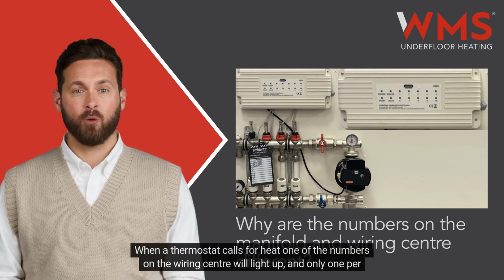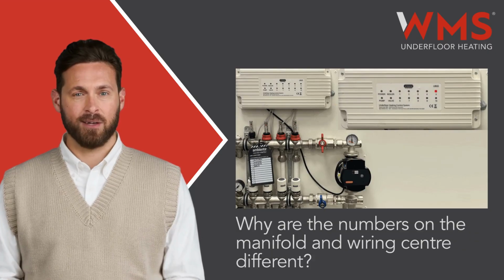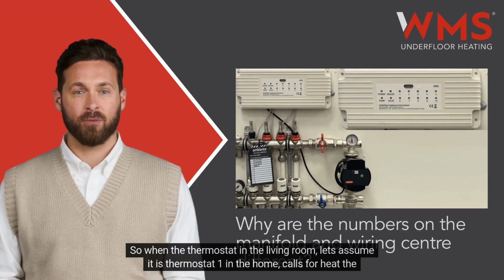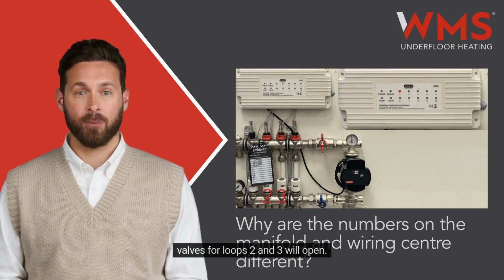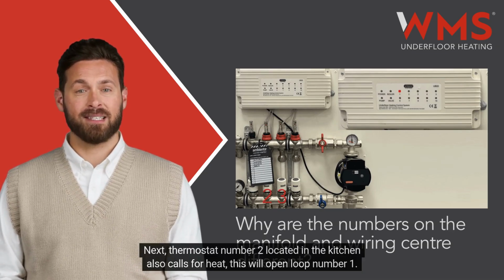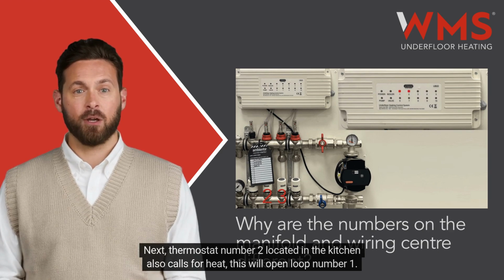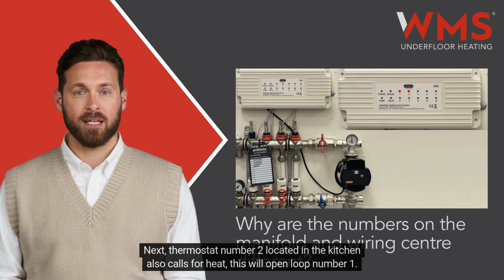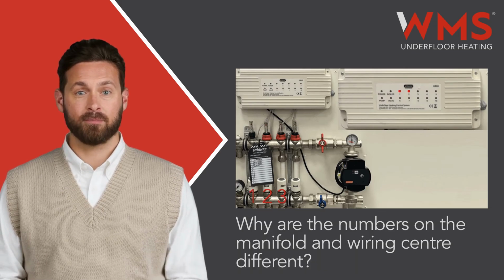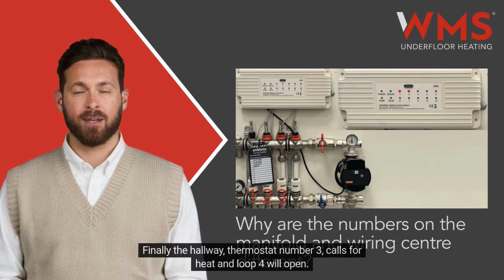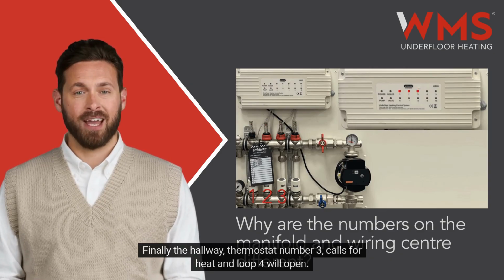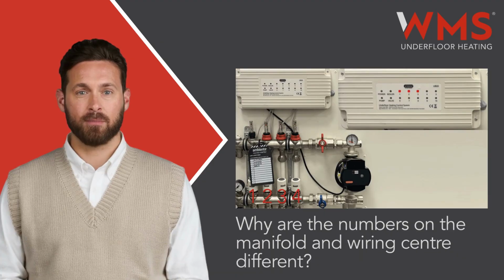When a thermostat calls for heat, one of the numbers on the wiring center will light up, and only one per thermostat. So, when the thermostat in the living room, let's assume it is thermostat 1 in the home, calls for heat, the valves for loops 2 and 3 will open. Next, thermostat number 2, located in the kitchen, also calls for heat. This will open loop number 1. Finally, the hallway. Thermostat number 3 calls for heat and loop 4 will open.